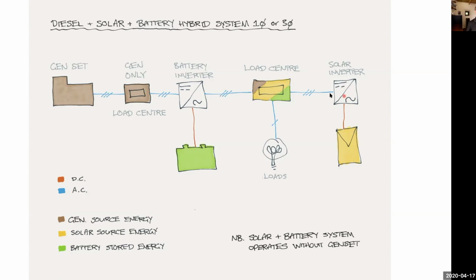The sizing of these two, the battery inverter and the solar inverter, are somewhat locked together though. You have to consider that if you've got 10 kilowatts of solar inverter power here, this battery inverter needs to be able to accept 10 kilowatts or in some way curtail it. Because if it can't accept the full power of that solar inverter, you're going to basically damage that battery inverter. So that's a design consideration based on the product that you're using.